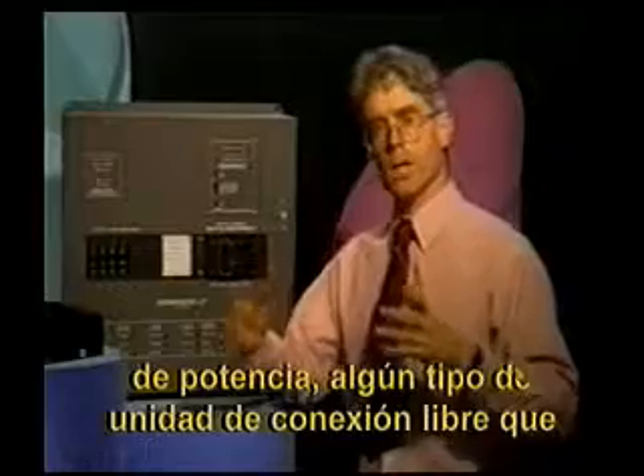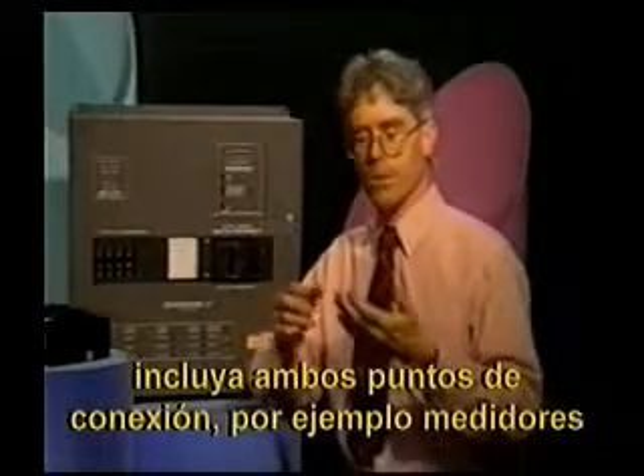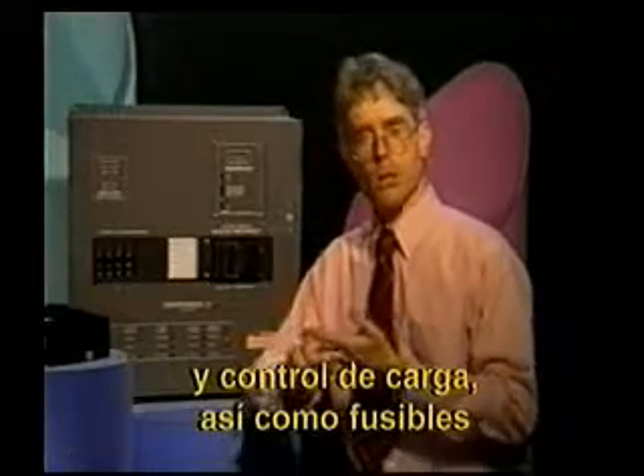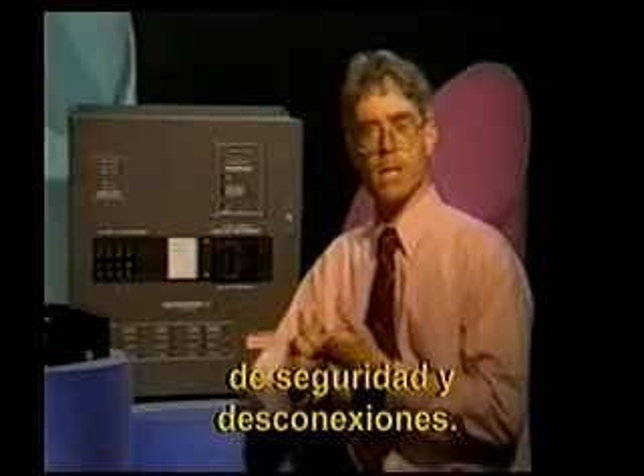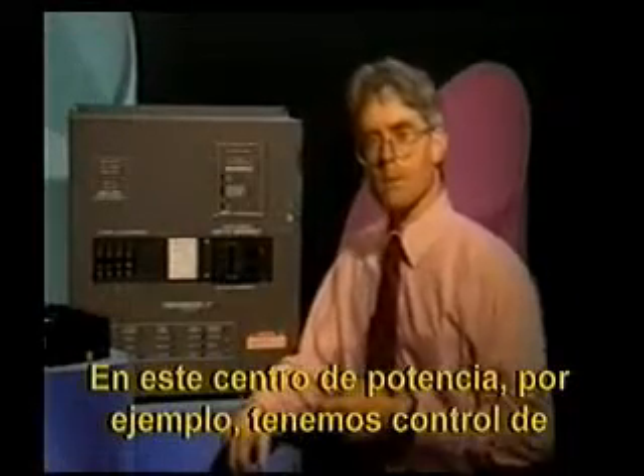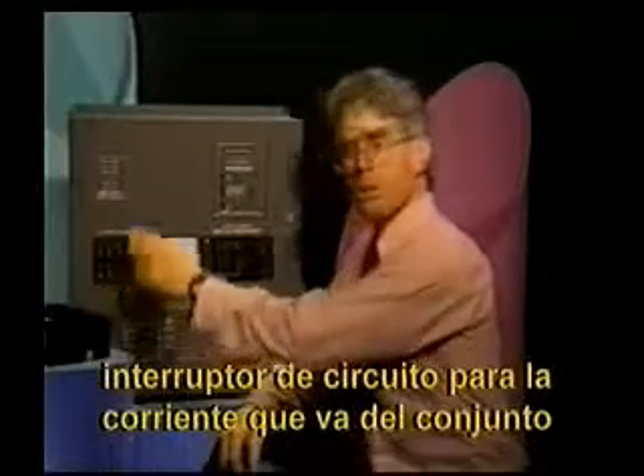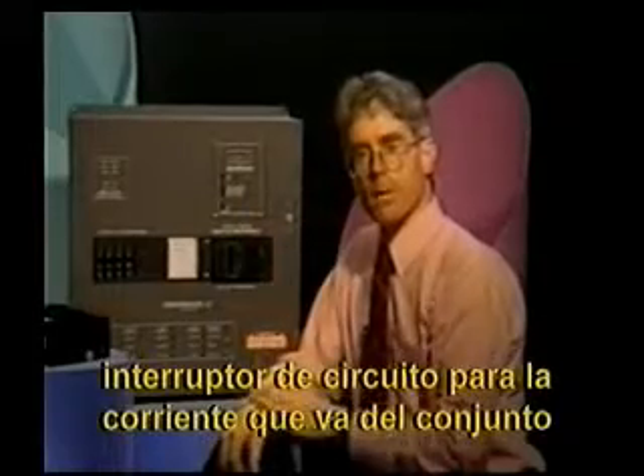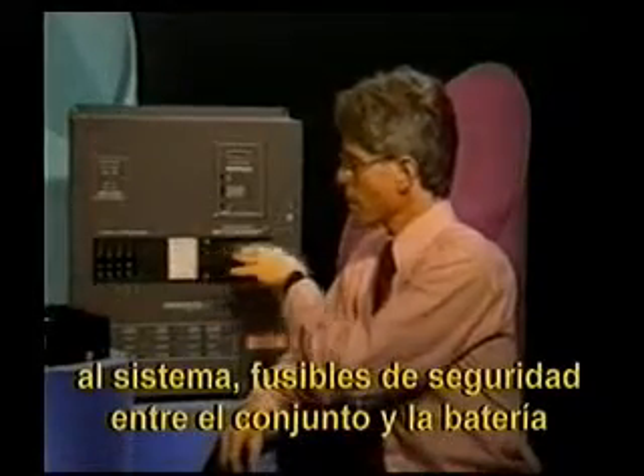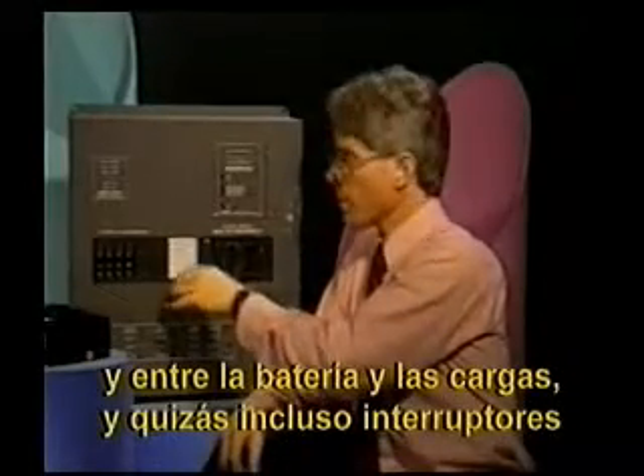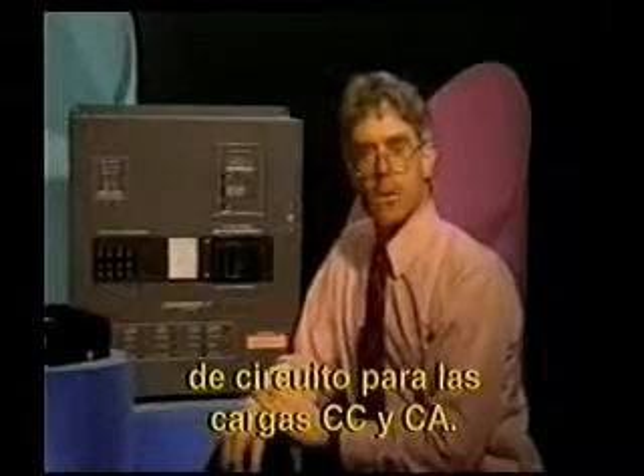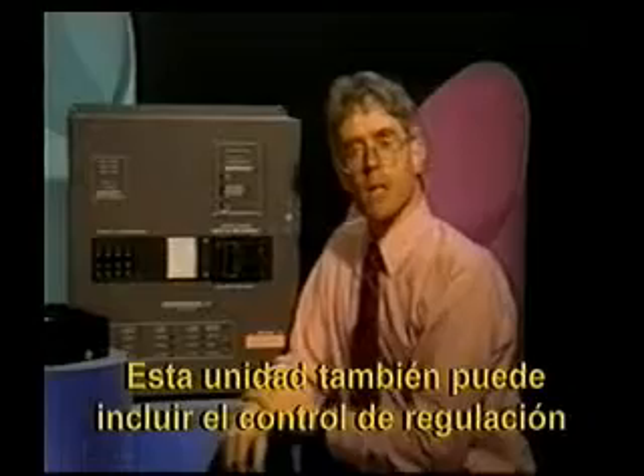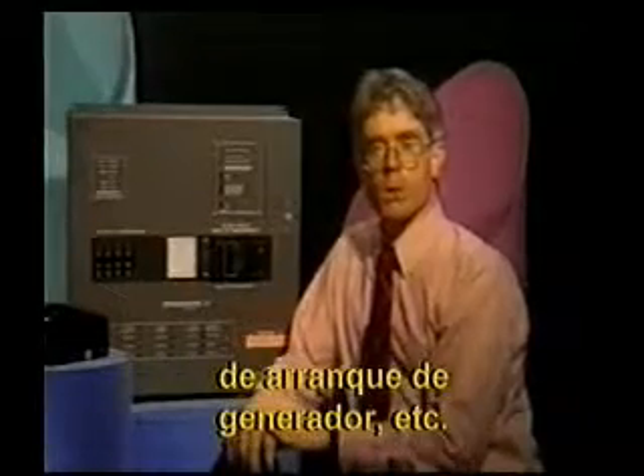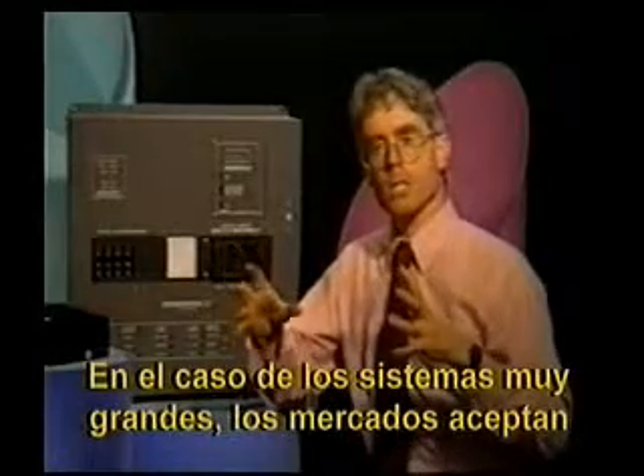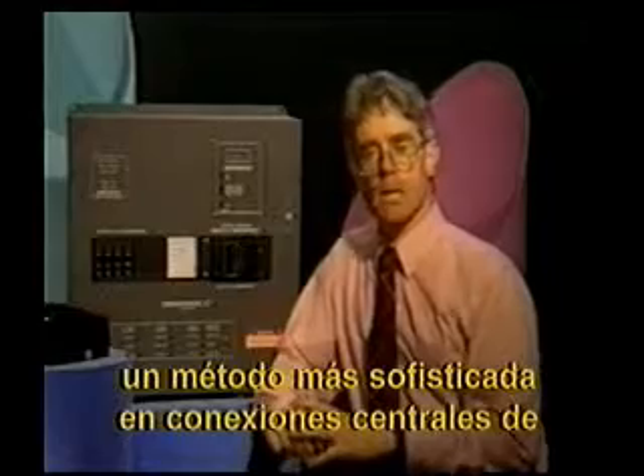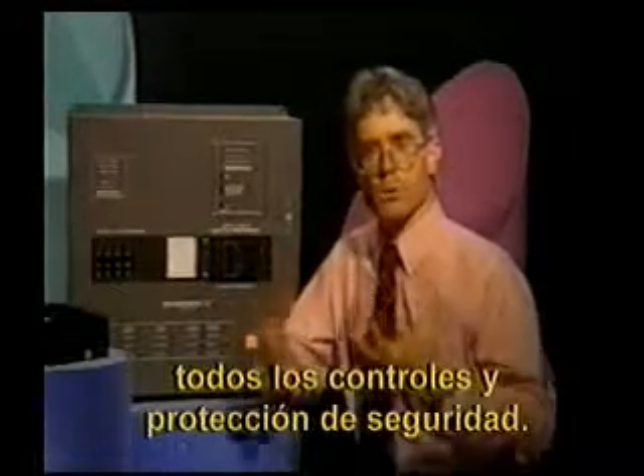Some sort of pre-wired unit that is your central wiring station that includes both connection points, perhaps metering points and charge control points, and your safety, fusing, and disconnect. An example might be this type of power center, where we would have circuit breaker control for incoming current flowing from the array into the system, safety fusing between the array and battery, and between the battery and the loads, and perhaps even circuit breakers for our DC and AC loads. This unit might also include our charge regulation control and metering, as well as generator starting control and so on. I think if you're looking at larger and larger systems, we're now dealing with markets that will accept a more sophisticated approach to central wiring of all of our controls and of our safety protection.